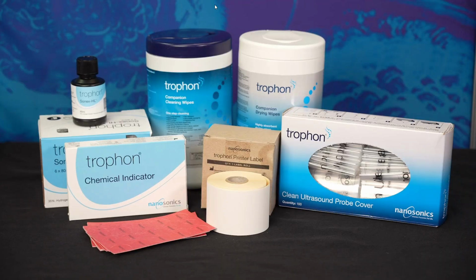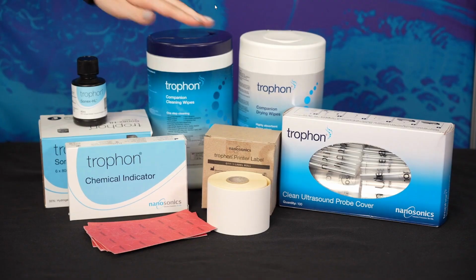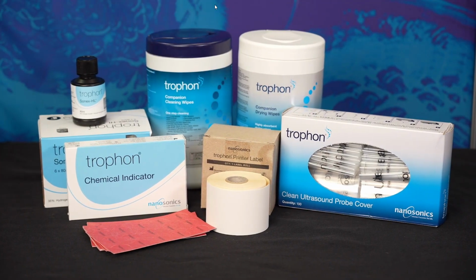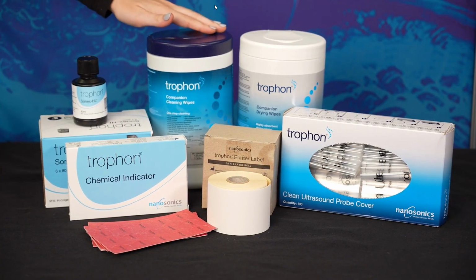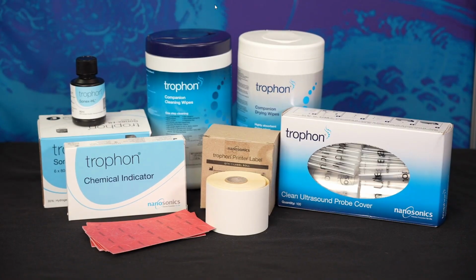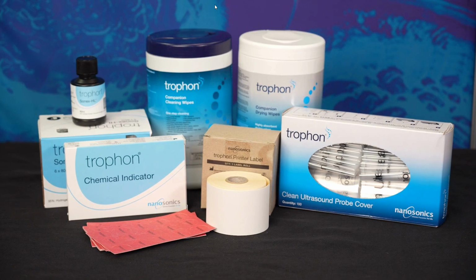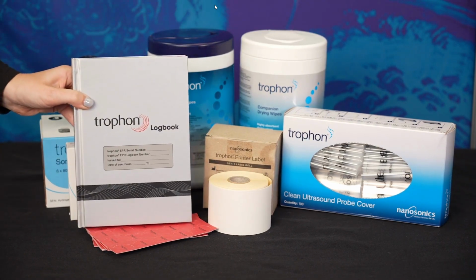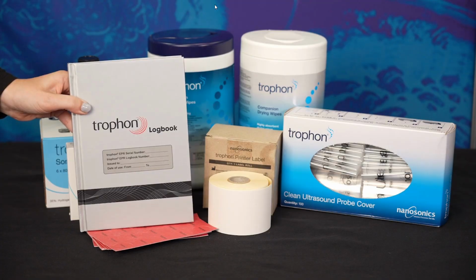Some additional optional supplies include Trophon clean covers for probe storage, Trophon companion cleaning and drying wipes, which are compatible with most ultrasound equipment and can be used as a low-level disinfecting wipe. Please note that most ultrasound manufacturers state in their IFUs that paper towels should not be used to dry the probe since they may be too abrasive for the probe, especially the lens. And there are also logbooks to document your high-level disinfection cycles.